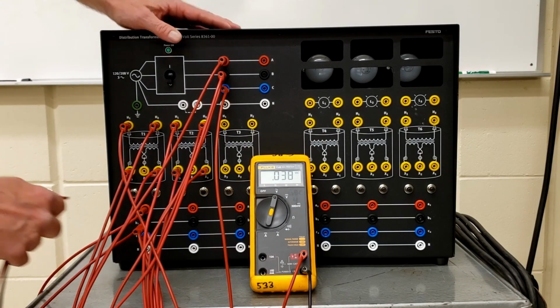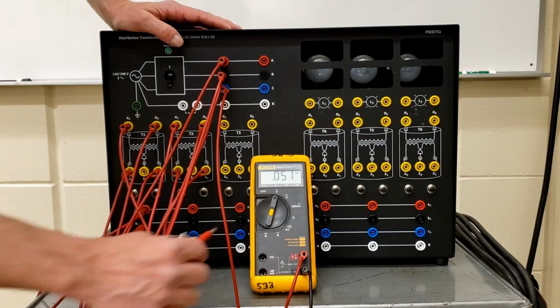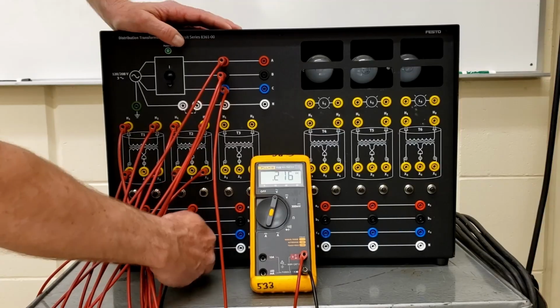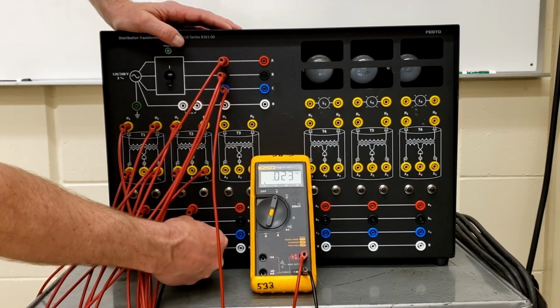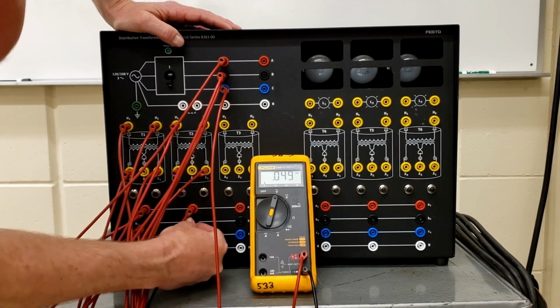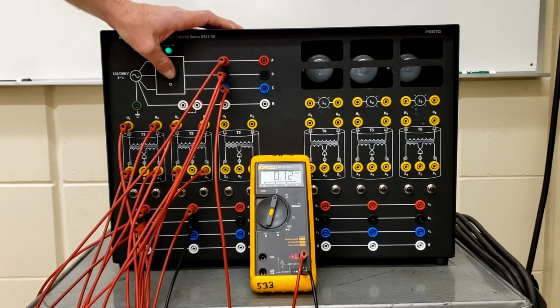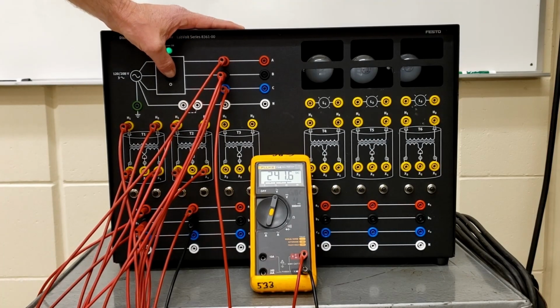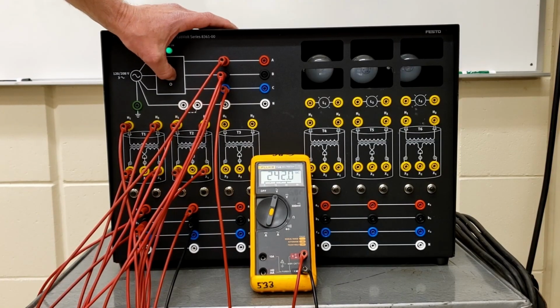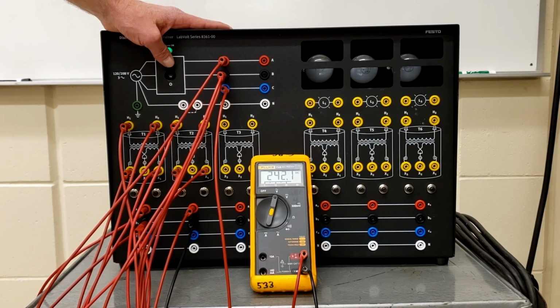Let's take a look at the voltage between the A and the B phase. A1 and B1. Okay, so we got 240 there. So we have the same as we had before with the closed delta in that X1 and X2 gives us 120, X2 to X3 gives us 120. The sum of those guys are giving us 240 volts out.